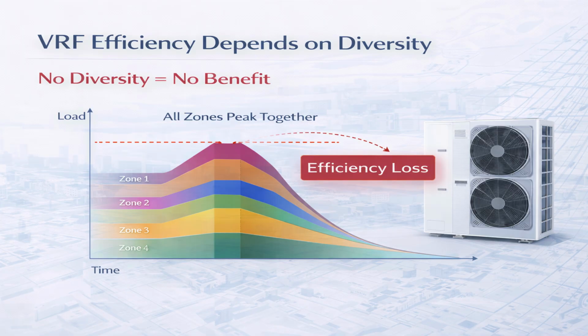However, problems begin when all indoor units peak at the same time. In that situation, the outdoor unit is forced to operate near full load for extended periods. Capacity modulation becomes limited, energy consumption increases, and the system loses much of the efficiency advantage it was selected for. When this happens, the VRF system effectively behaves like an oversized DX system, but with significantly higher initial cost and complexity. This is why diversity should never be assumed. It must be evaluated realistically based on the space usage, schedules, and occupancy pattern. Without true diversity, the benefits of a VRF system quickly disappear.